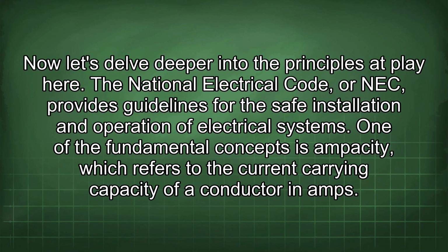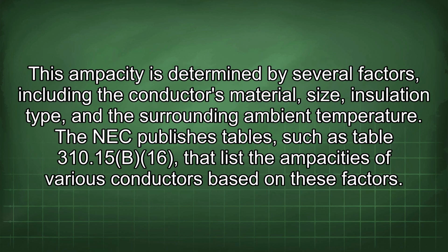Now let's delve deeper into the principles at play here. The National Electrical Code, or NEC, provides guidelines for the safe installation and operation of electrical systems. One of the fundamental concepts is ampacity, which refers to the current carrying capacity of a conductor in amps. This ampacity is determined by several factors, including the conductor's material, size, insulation type, and the surrounding ambient temperature.